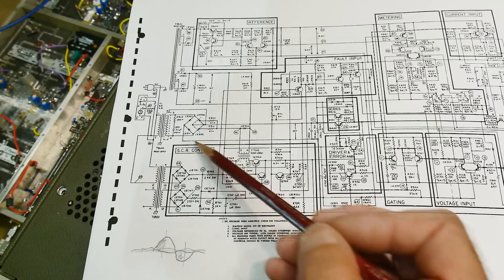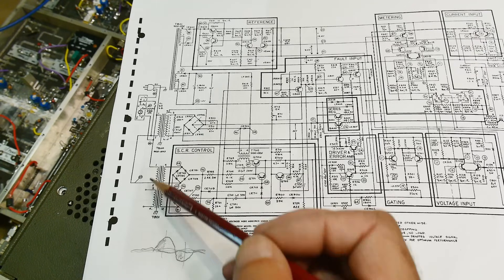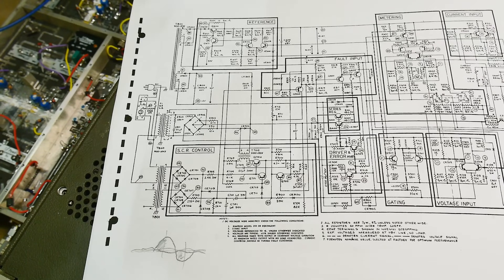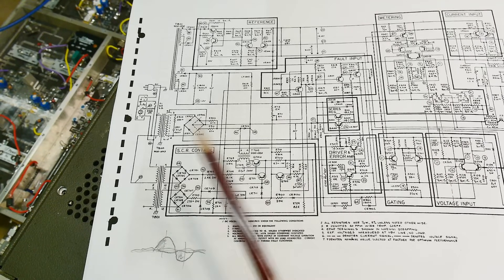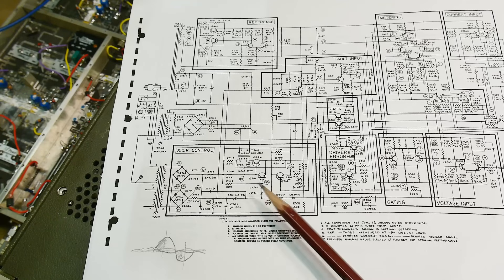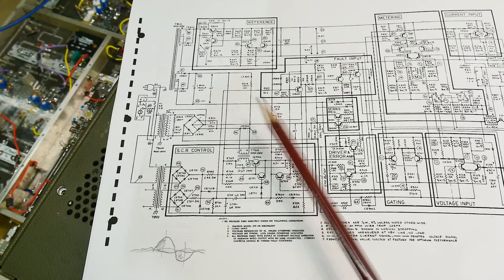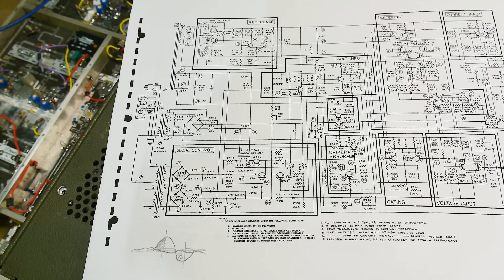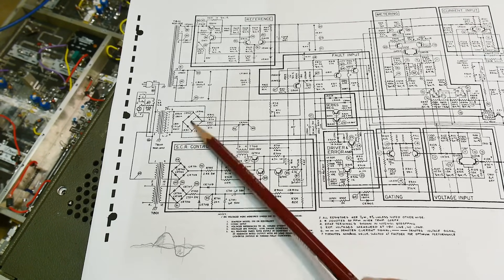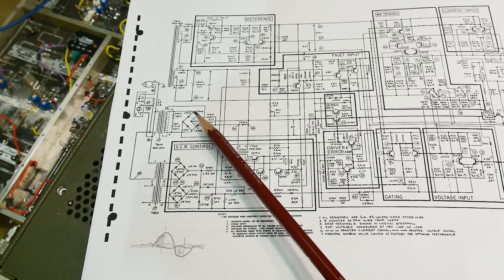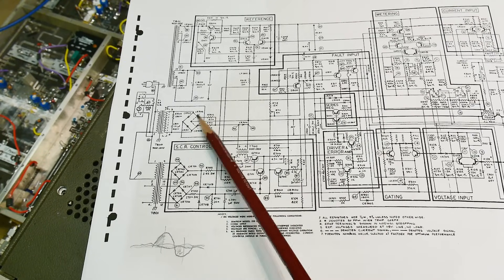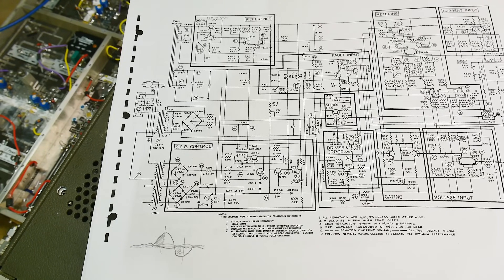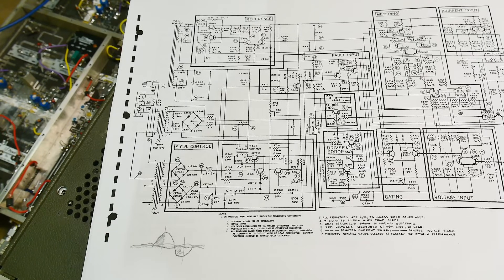So these SCRs are in the plus side of the bridge rectifier and they are controlled with this transformer. So this transformer can turn those guys on and off. You monitor the waveform by these two bridges here, and then you program in some voltage. So it's going to find the voltage that it wants to be. Let's say it always wants to be two volts more than the output. It's going to get that information from somewhere. I haven't looked at this yet, but it will then either turn these diodes on or not. That's basically what these SCRs are going to be, gated diodes. Now, if they went bad, they wouldn't be charging that capacitor up at the right time and they wouldn't be giving you the current. So my suspicion is that this power supply probably has a fault in the SCR control. And I have never troubleshot one of those before, so it will be interesting.